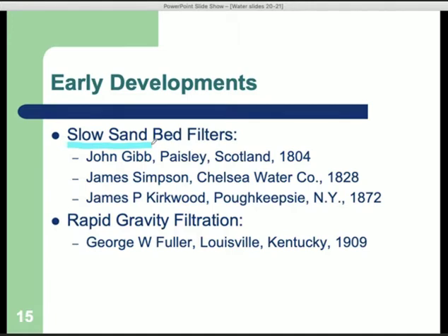And then you put your water into that swimming pool, and the water filters through the sand. But the dirty stuff, the heavy stuff that I mentioned earlier on, these sort of solids, they start sticking to the sand a little bit and form a breeding ground for bacteria. So these sand filters would be nothing else than a very coarse filter for solids. And onto these dirty solids, you would then have bacteria growing, and that is the actual treatment.